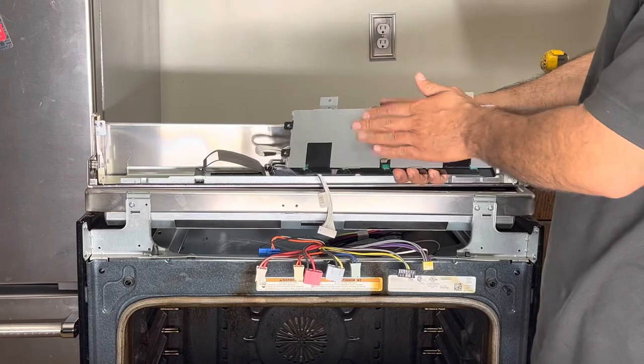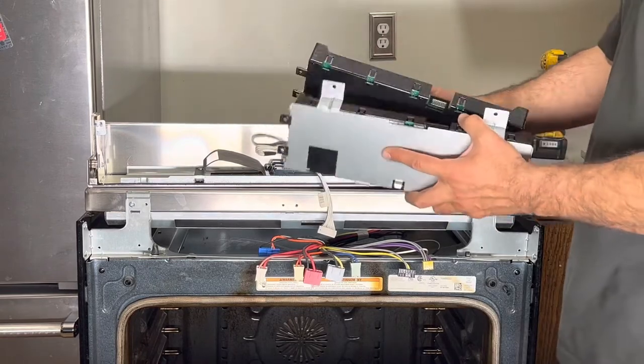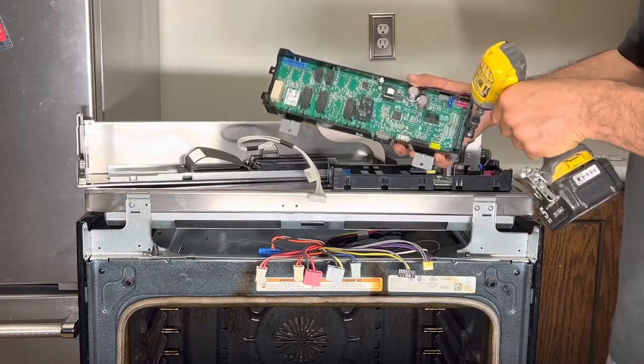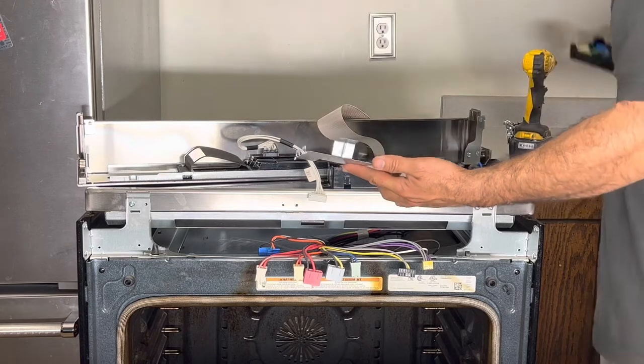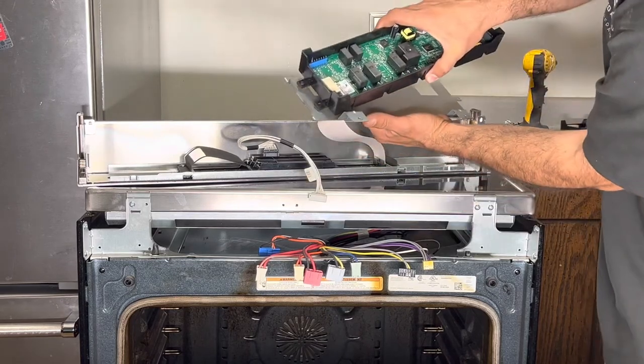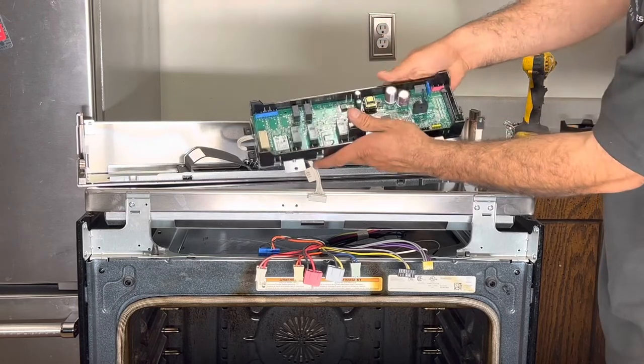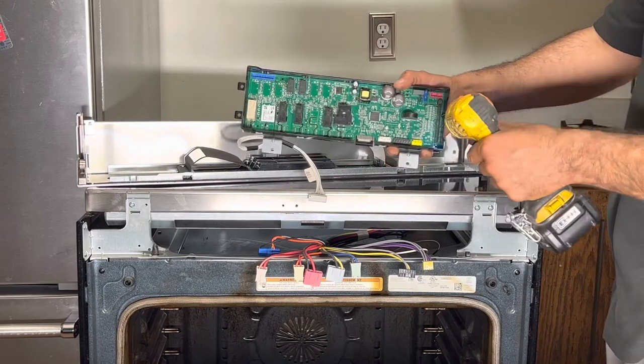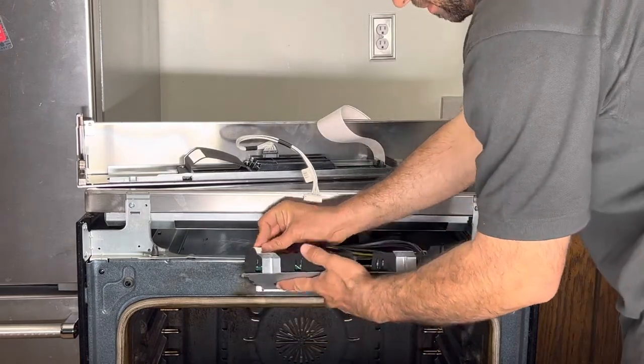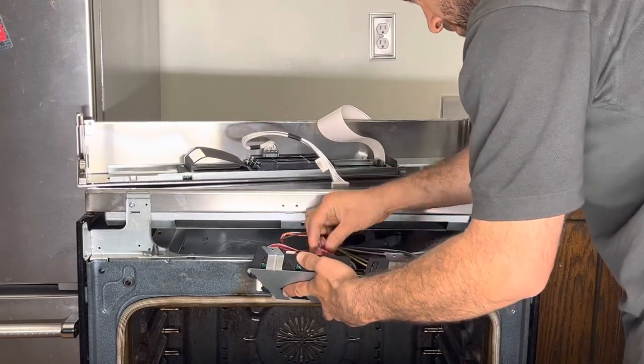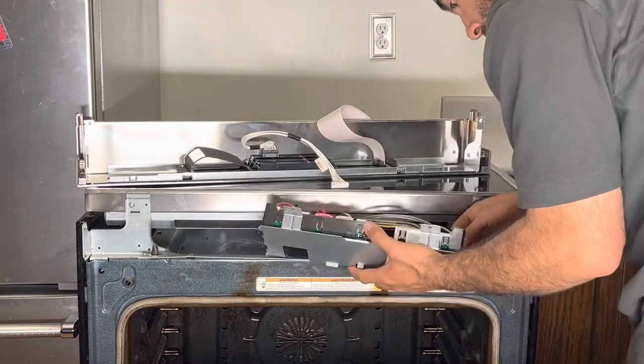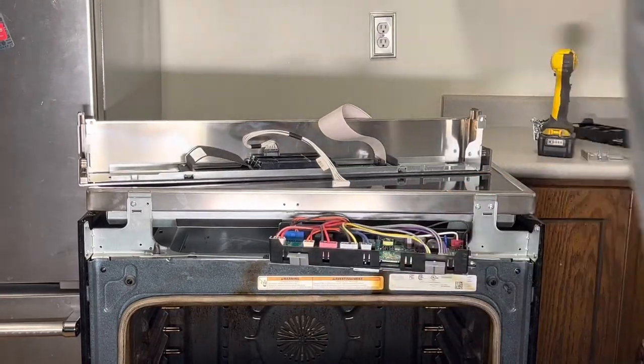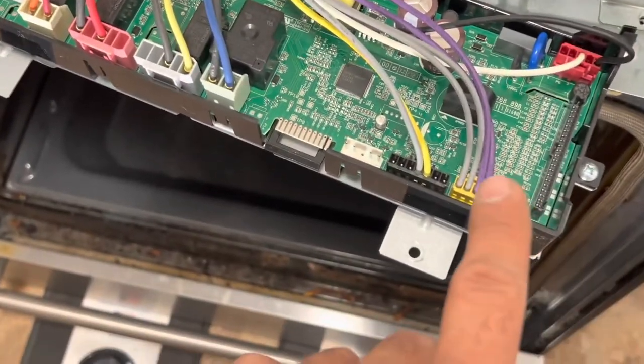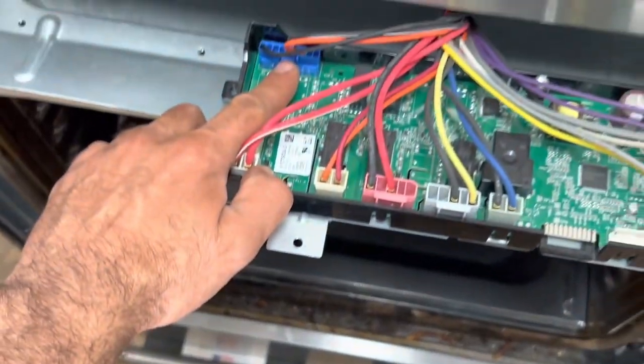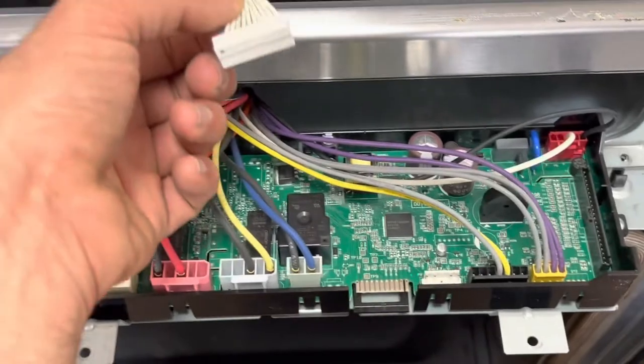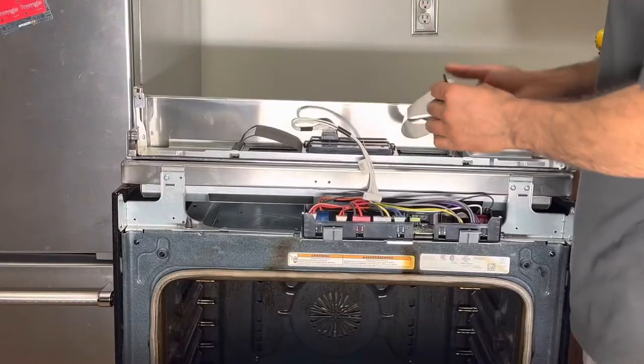This metal piece also needs to be taken off and reinstalled on the new board. There is one screw. There are two clips that get inserted in there. Push, and then you can add your screw back in. Double check your connections, see the yellow, the black, red, the blue, and then your ribbon cable and this cable from the display. Your ribbon cable.